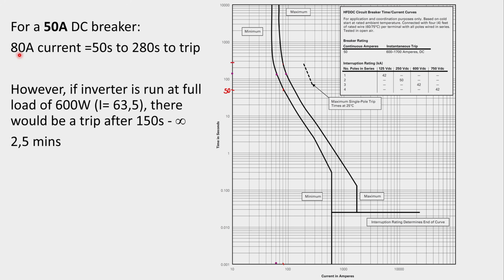Will it trip for 80 amps? Yes, it will trip for 80 amps, but it will take a bit of time. Now, we don't want the circuit breaker to trip for the inverter just running at full load. If somebody connected full load and wants 600 watts from that inverter, the inverter should be able to provide it if it's a good quality inverter. Now, maybe it won't be able to provide it for 20 minutes, but it should be able to provide it for a bit of time. So we don't want the circuit breaker to trip just for normal load conditions.